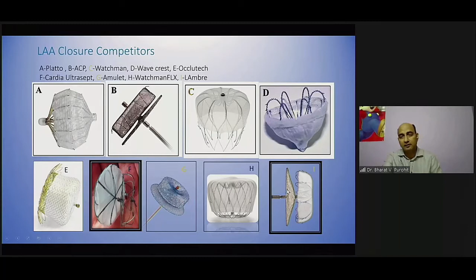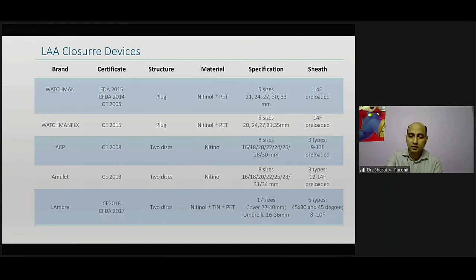The advantage of Lambre is it can be introduced through a very small sheath, of maximum 8 to 10 French diameter, whereas all other devices need at least a 10 to 14 French sheath. What is very interesting with Lambre devices is that it comes in two different types: one is a special device, another is the conventional one. A little bit has been told by Dr. Ranjan also, that in the conventional devices, the difference between the umbrella and the proximal cover is between 4 to 6 millimeter. Whereas in a special situation where you have a double lobe, or when the orifice is very big, you can choose a special device where the proximal cover is almost 12 to 14 millimeter bigger. So if you have a distal umbrella of 16, then the proximal cover will be 30.